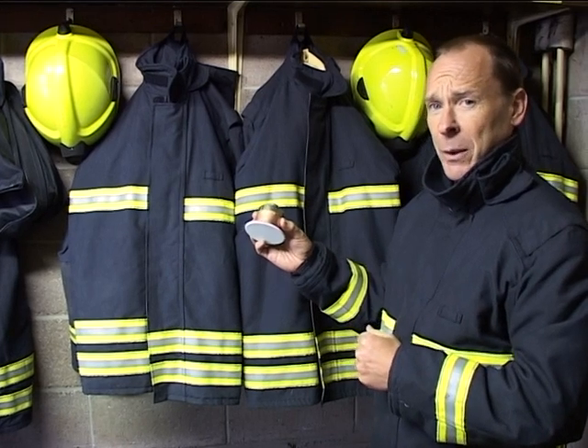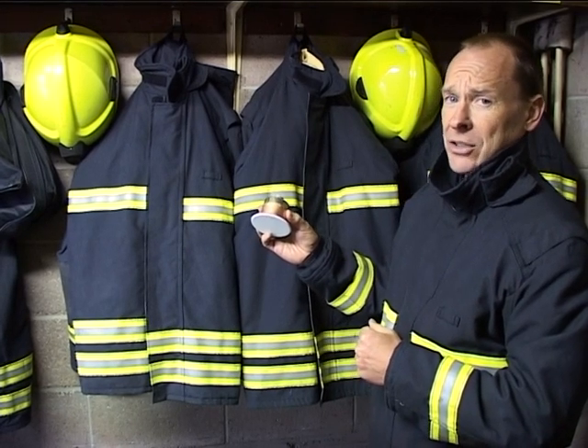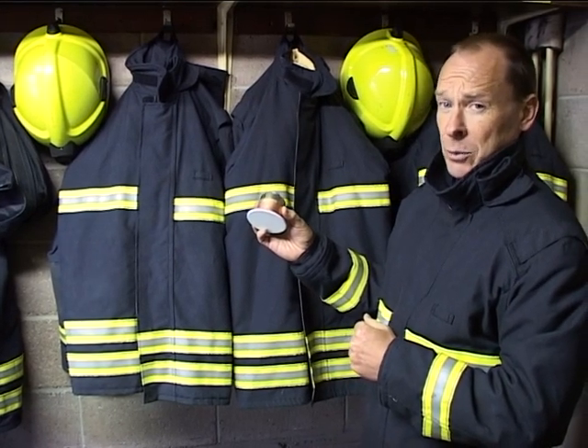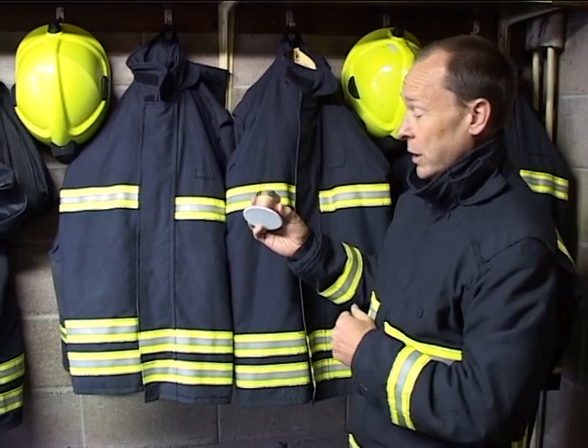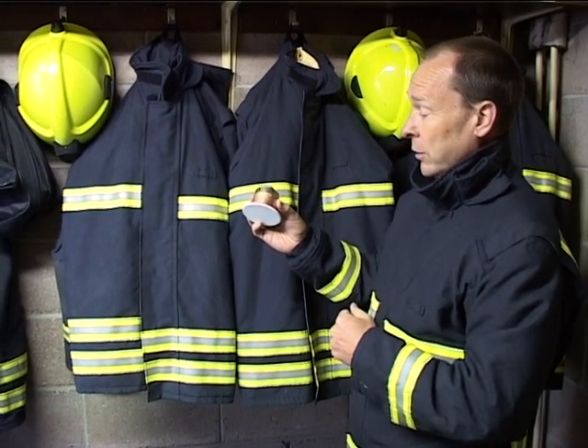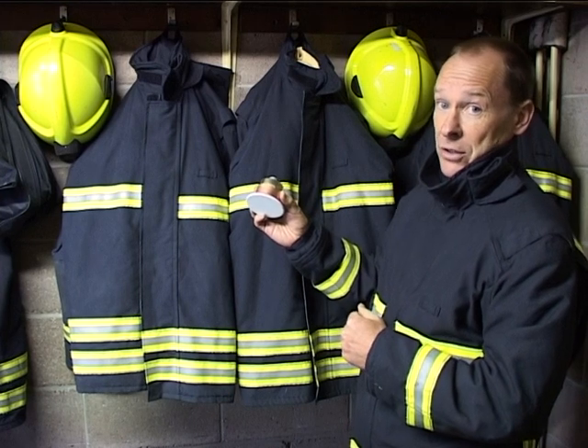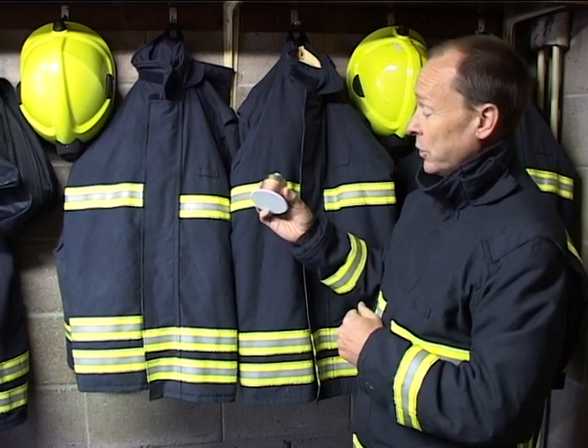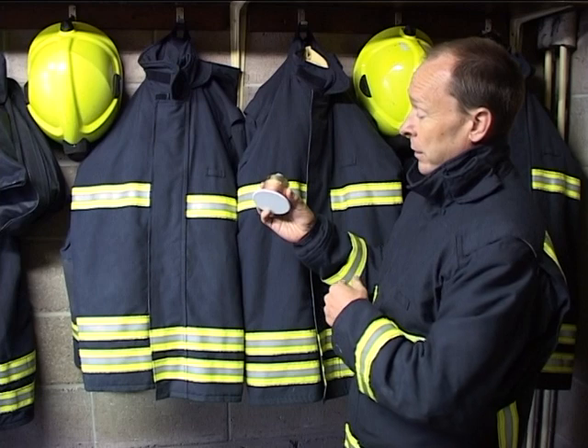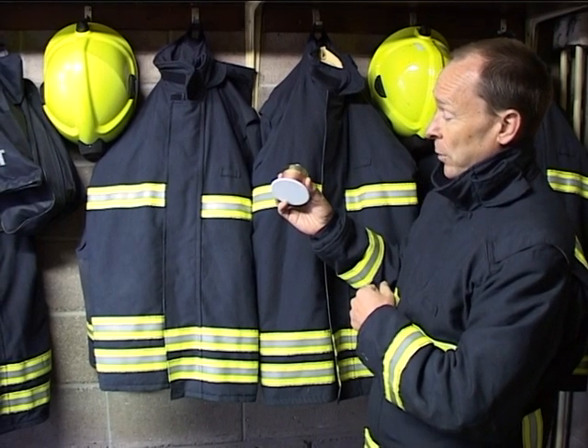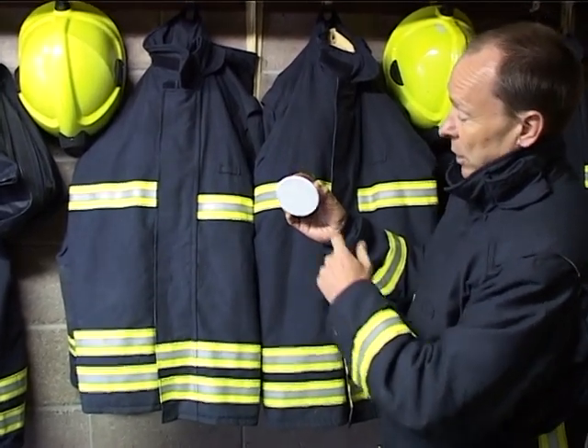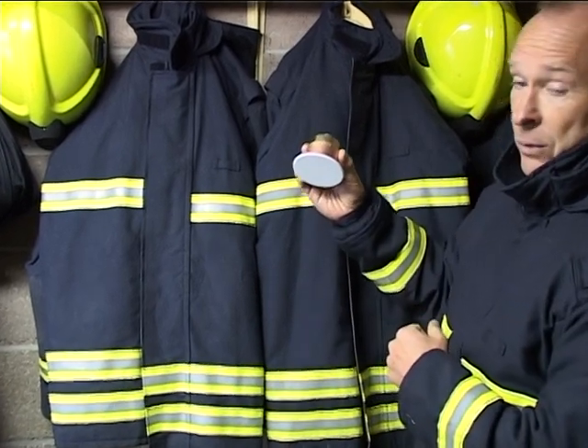One of the common myths about sprinkler systems is they can go off accidentally, a bit like a smoke detector with smoke from burnt toast. That's simply not the case. Only the heat from a fire will set off a sprinkler system. It's proven technology. I'm holding here a sprinkler bulb from a residential sprinkler system. This is the blanking plate that sits flush with the ceiling.